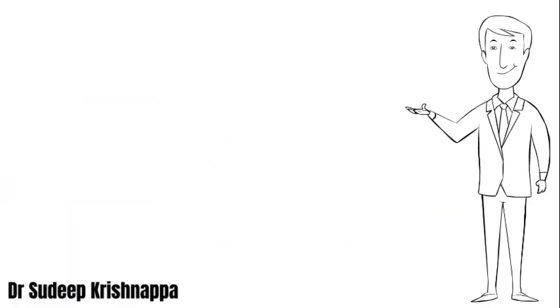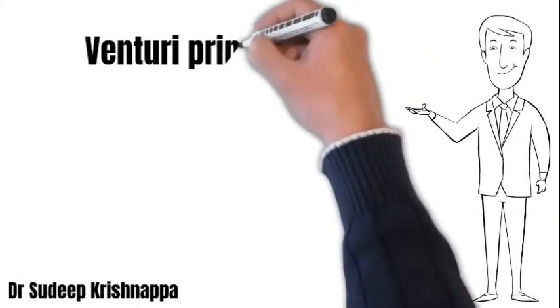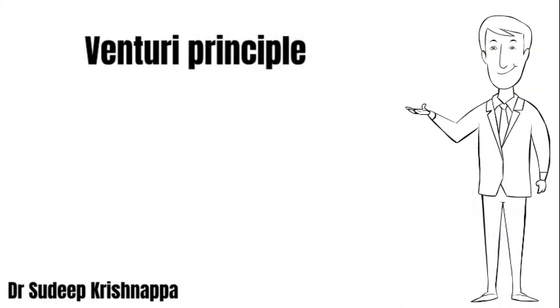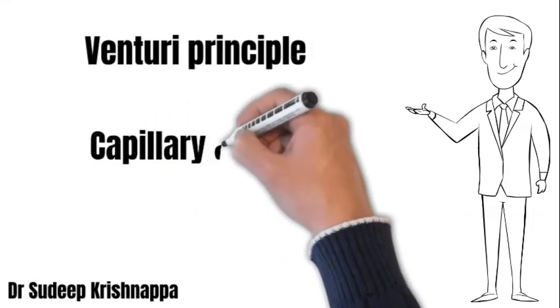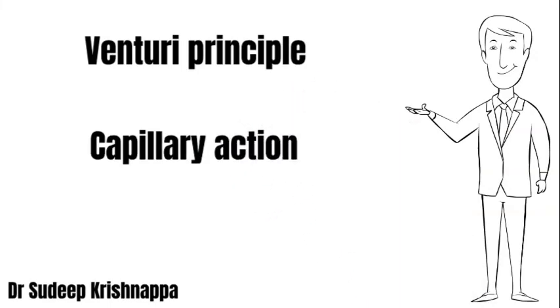As mentioned earlier, these nebulizers come in various shapes. For the purpose of explanation we have chosen two of them, but they do come in several different shapes. The essential working principle is the same: the Venturi principle generates a pressure drop and subatmospheric pressure; capillary action suctions the fluid present in the chamber towards the orifice; and the jet shatters the liquid film into aerosol particles against an internal baffle. Hope this was useful — thank you.